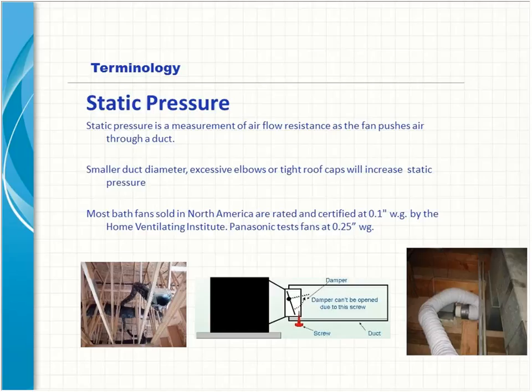So a very interesting call to go out on. We were called out, of course, because the equipment was failing. But when we got out there and did the investigation, we found that there was just too much static pressure because the damper was pinned shut and the exterior termination was painted shut. So once we fixed all of that, everything was fine.